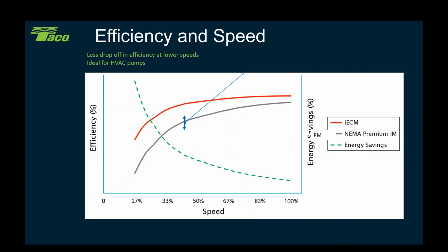So where this is really important to understand is that permanent magnet motors don't lose as much efficiency as we reduce the speed, okay? Unlike an induction motor, that loses more efficiency the slower we go. That induction motor starts to get less efficient. Permanent magnet motors don't have that drop off in efficiency until you get down around 30% of design max speed. That's when they really start to lose their efficiency, okay? Whereas an induction motor, at about 55 or 60% of design max speed, the efficiency starts to go, and as you get down below 30%, it really falls off to next to nothing, okay?